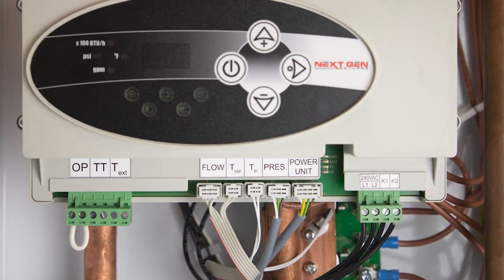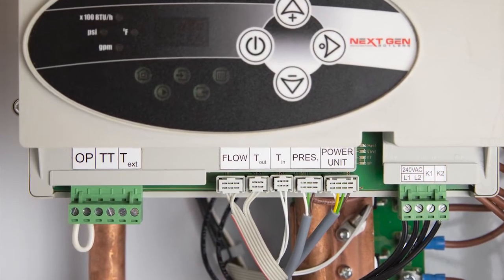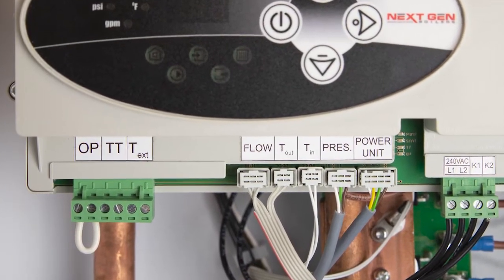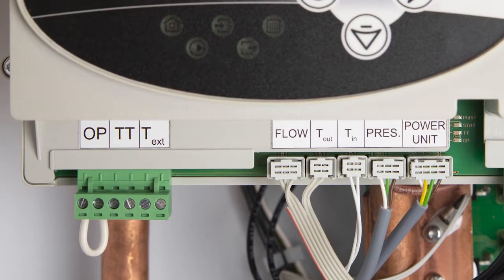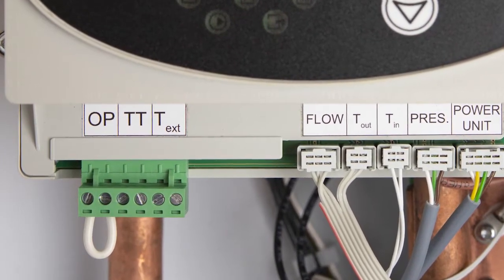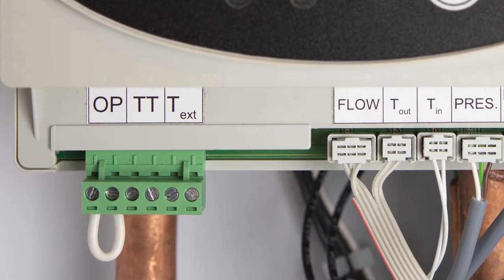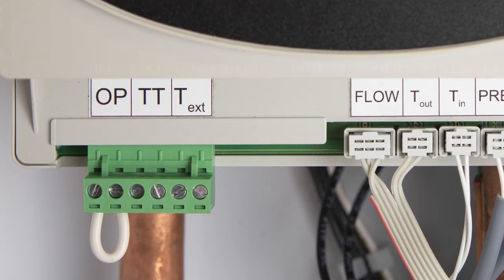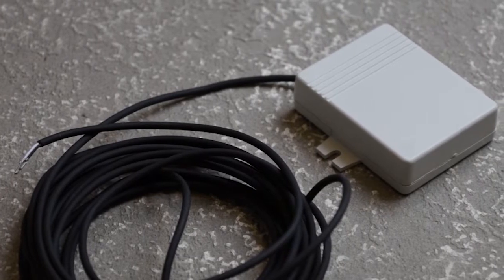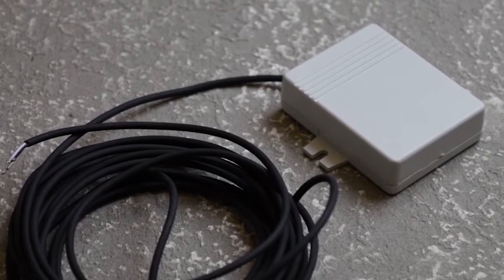The NextGen boiler is equipped with an optional ability to receive a utility signal for an off-peak connection. This connection is normally closed and can be found on the bottom left corner of the control panel under OP. If you do not have the boiler connected to a utility radio receiver, please keep this connection closed with the white wire which is pre-installed with the boiler. You can consult with your local utility about the off-peak installations.